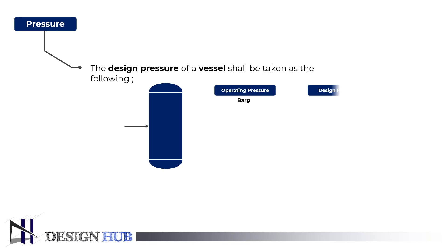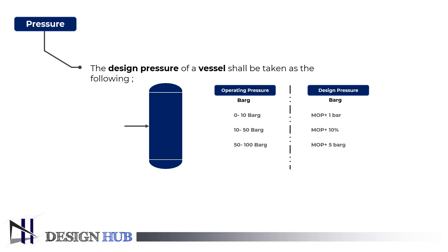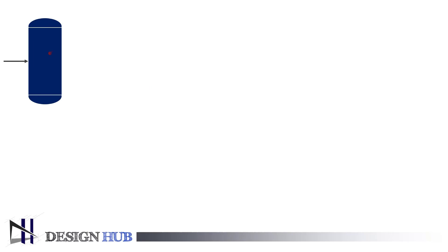For example, for 0 to 10 bar operating pressure, vessels are generally designed at maximum operating pressure plus 1 bar margin. Similarly, you can see other ranges as well.